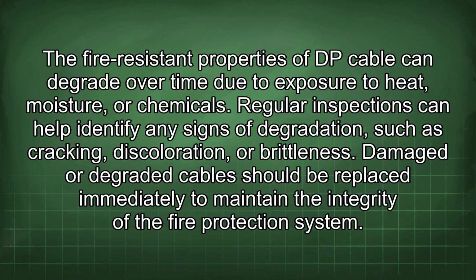The fire-resistant properties of DP cable can degrade over time due to exposure to heat, moisture, or chemicals. Regular inspections can help identify any signs of degradation, such as cracking, discoloration, or brittleness. Damaged or degraded cable should be replaced immediately to maintain the integrity of the fire protection system.